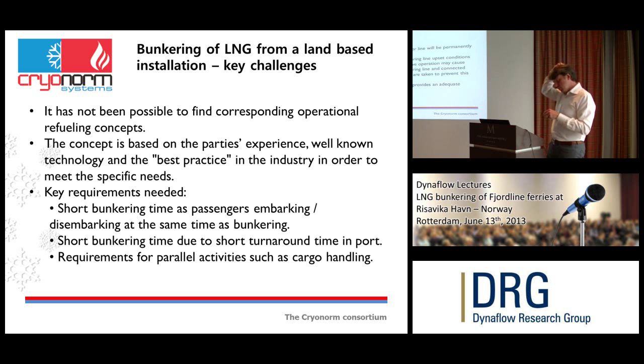At idle conditions, the bunker line will be filled with LNG. We had to make sure that if the system sits idle for 24 hours, even in a vacuum insulated line where insulation is extremely good, there will still be heat inleak through radiation, convection, and conduction, causing a temperature increase of the LNG in that line.